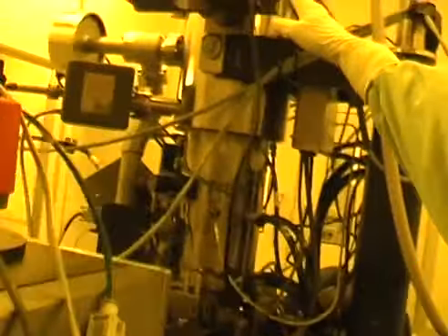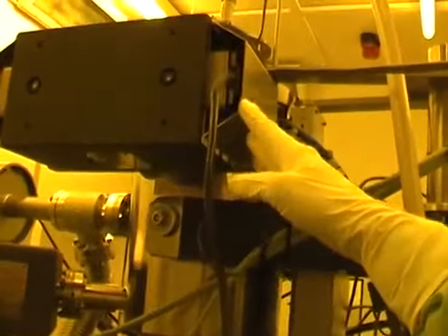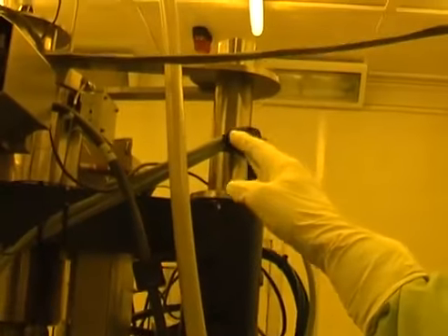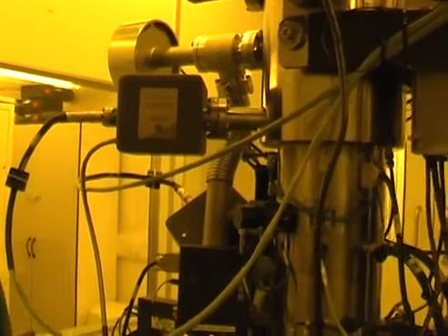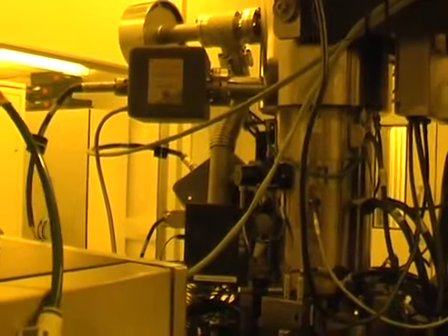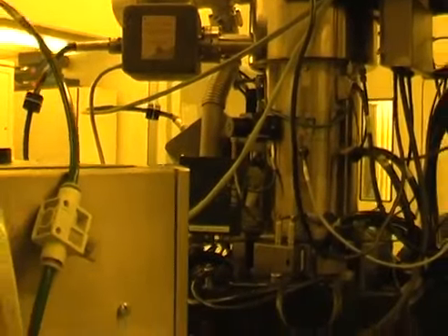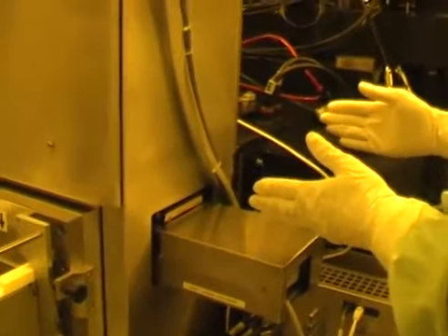Other things which you might recognize are pumps. This is an ion getter pump. There's another one at the top. There's 2 which pump out the gun chamber. There's another one here halfway down which keeps the column under a good vacuum. There are 2 turbo pumps which are underneath the system. You can't see them because of the covers. One under here which is the airlock pump, and one under here which is the system pump.